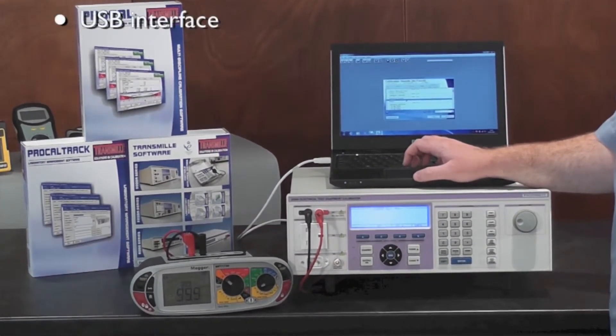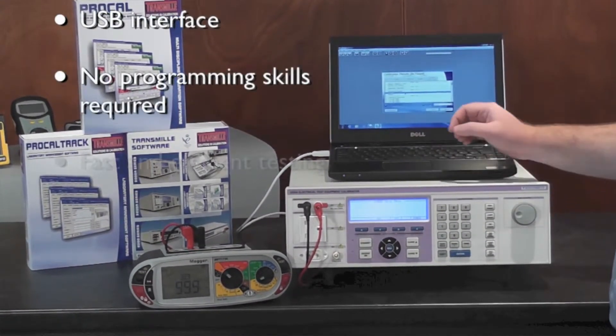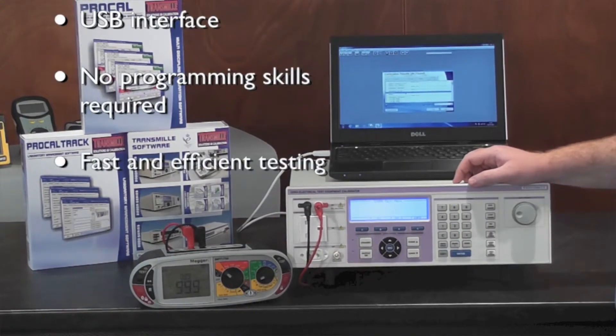When connected to a computer running our PROCAL software, procedures can be written that automatically control the 3200A, enabling fast calibration of testers.